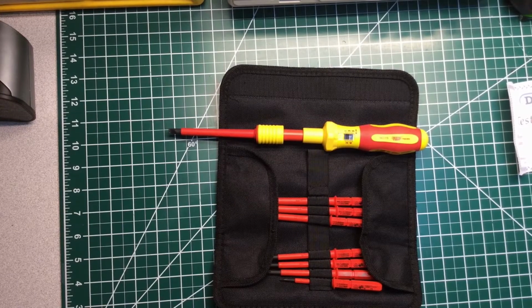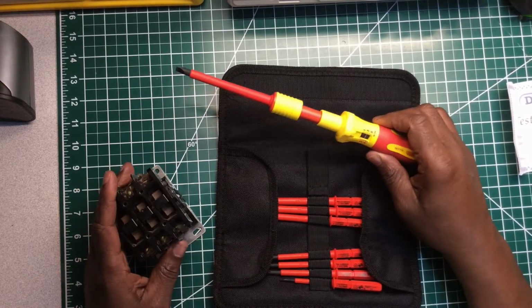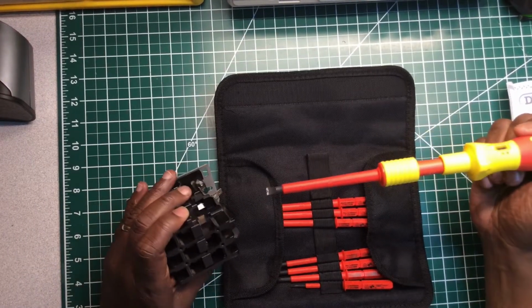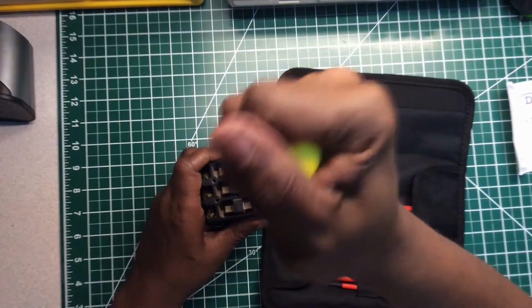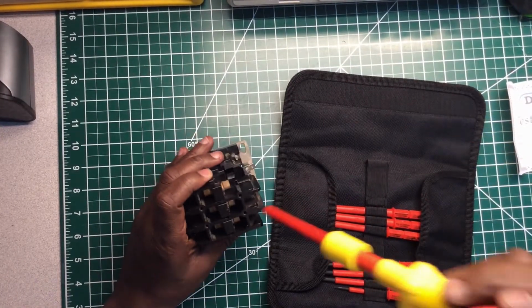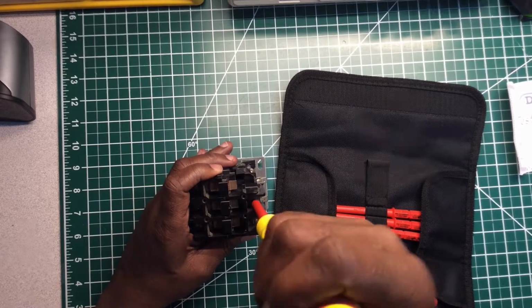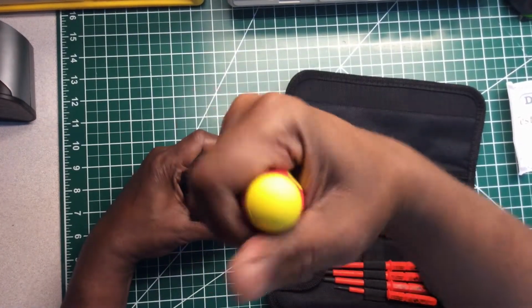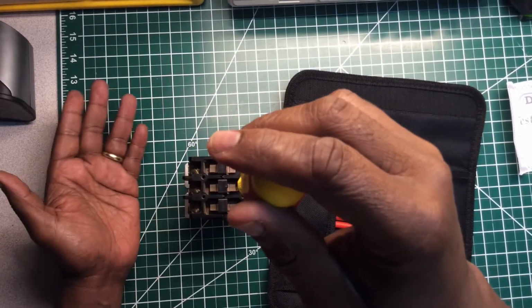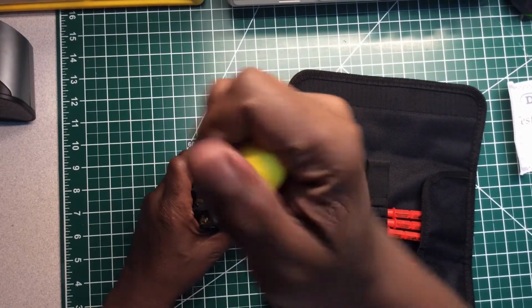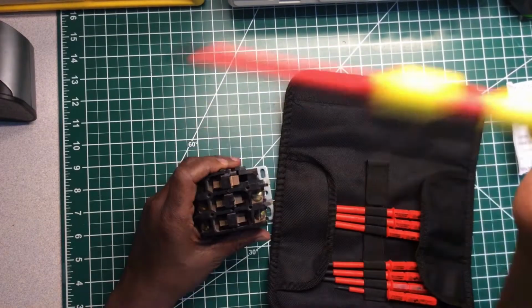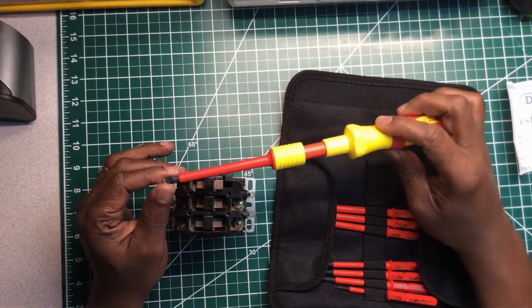I have an old contactor here, and it's rated for 35 pounds. I'm going to leave it on number 4, which is 36 pounds, and show you how it will sound when it clicks. It doesn't go any more. I also recommend when you're making any torque connections, always loosen it up first if it's not loosened already, or if you're just doing preventive maintenance, you can loosen it up a little bit and then retighten. That's it, and it won't go any further. That's why it keeps clicking.